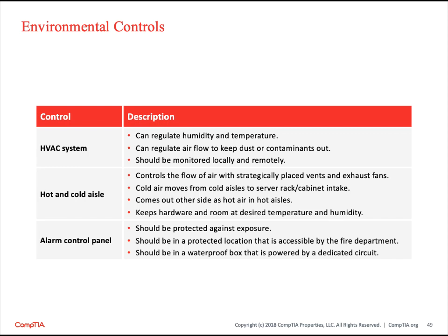It's recommended that these temperatures are between 72 and 76 degrees Fahrenheit in a computer facility, and we should keep our humidity somewhere between 40 and 60%, right?